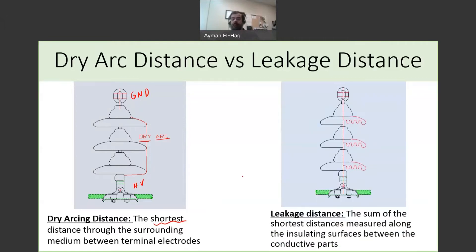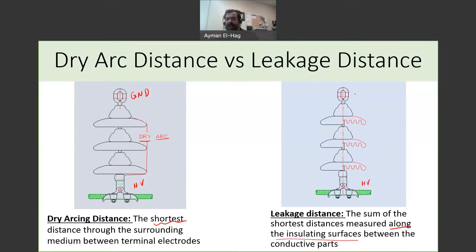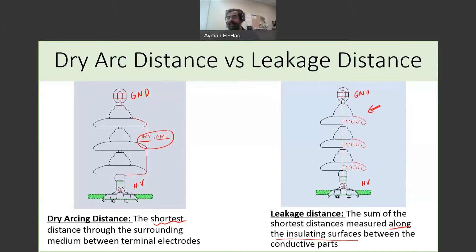The other definition is the leakage distance. The leakage distance is the sum of the shortest distances measured along the insulating surface. So, with this being the high voltage end and this being the ground end, the leakage distance — shown here in red — runs along the surface of the insulator. Obviously, the leakage distance is much longer than the dry arc distance.